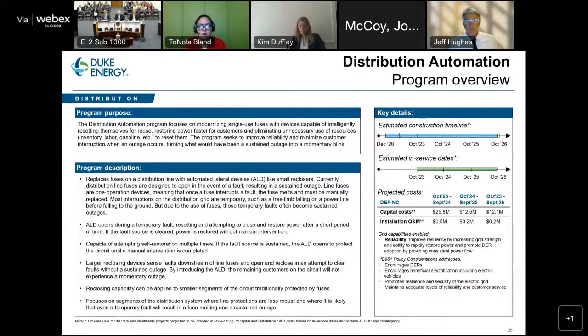Distribution automation is an existing program. It modernizes traditional protective devices on our laterals - focused on the laterals, not the backbone of our distribution circuit. This is accomplished by replacing a traditional single-use fuse with an intelligent electronic device, or automated lateral device. It's really a modern recloser for a single-phase device, and fits in the same location that a traditional fuse was.